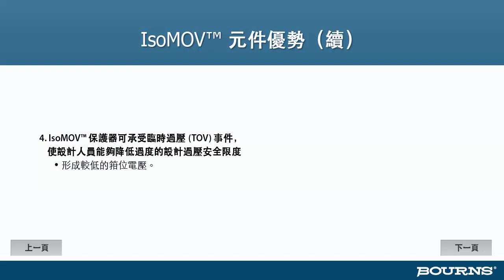The IsoMOV devices can tolerate AC voltages beyond their maximum continuous operating voltage rating for extended periods of time. Bourns has a technical paper on lab data that compares the IsoMOV protector to competing technologies. It's important to note that while the IsoMOV device will survive these higher voltages, they do not protect against them, and those higher voltages are being passed downstream. The load must be designed to withstand these higher voltages. Unlike many competing technology devices that will disconnect themselves from the line under these conditions, the IsoMOV device will be there after the event, continuing to protect against lightning and switching transients.